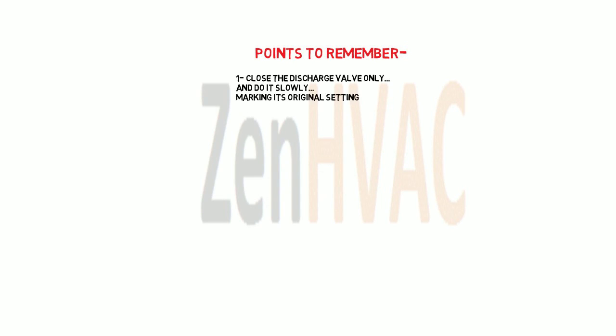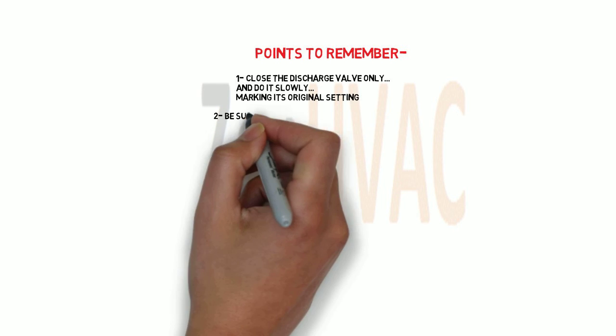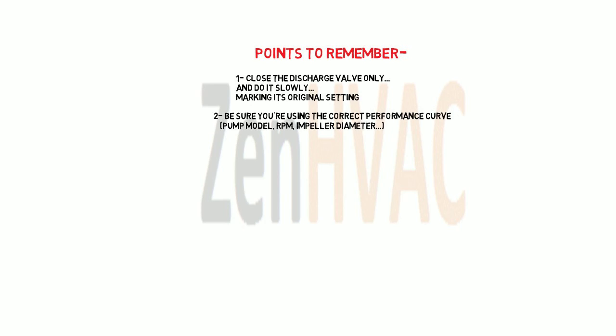Let's look at some points to remember. One, close the discharge valve only and do it slowly, marking its original setting. Two, be sure you're using the correct performance curve for the pump you're working with.